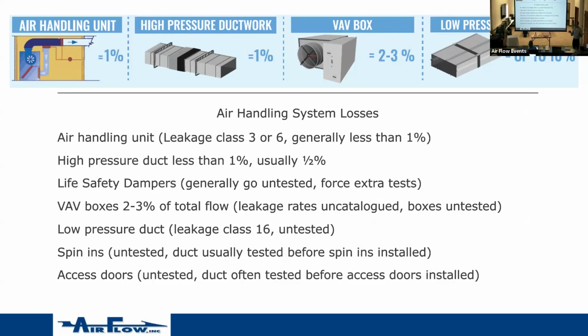All air handlers do have a pressure class that they meet, and it's usually in their specification. It still needs to be tested, right? And we talked about ductwork, roughly 1%. Again, we're following that pressure test. Our VAV box, 2 to 3%. Again, Mark's gonna talk about that.